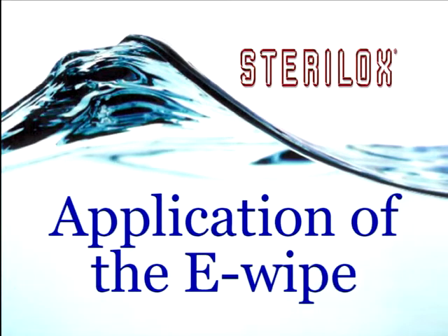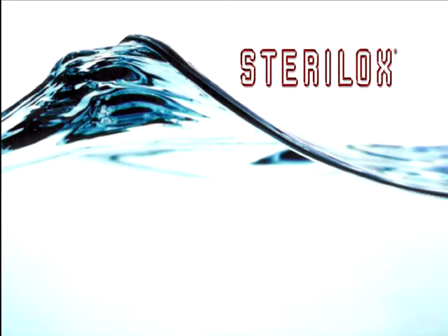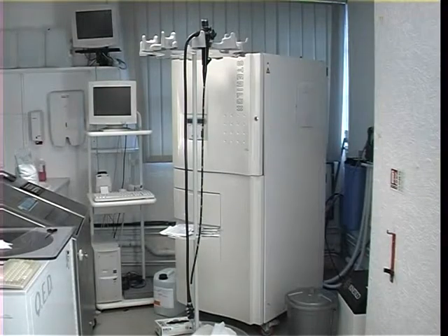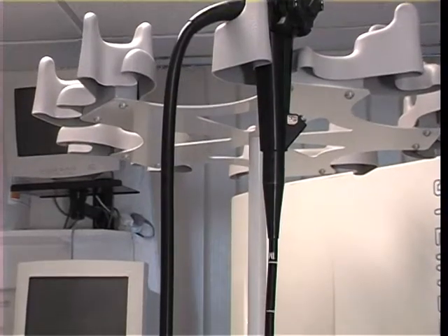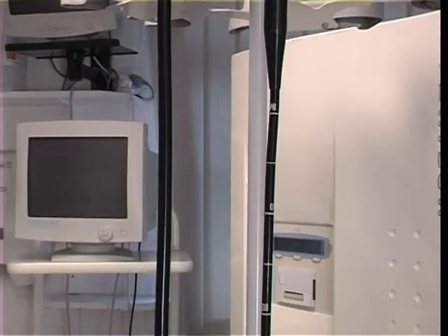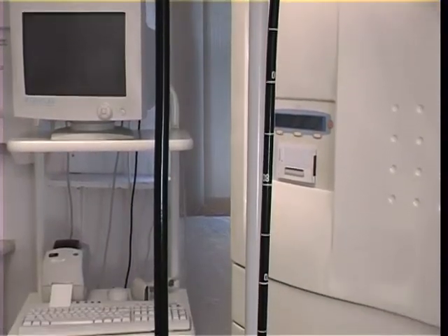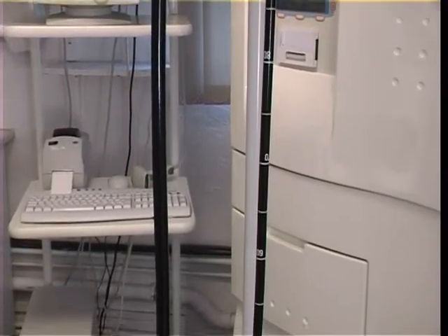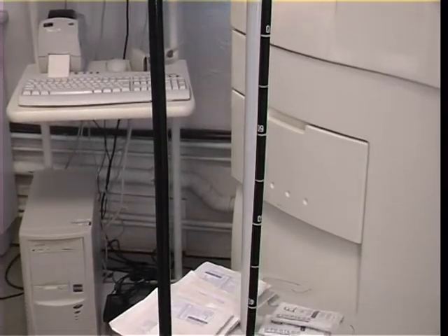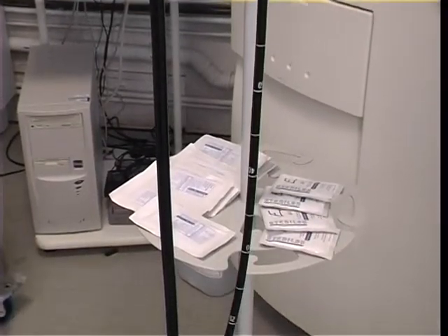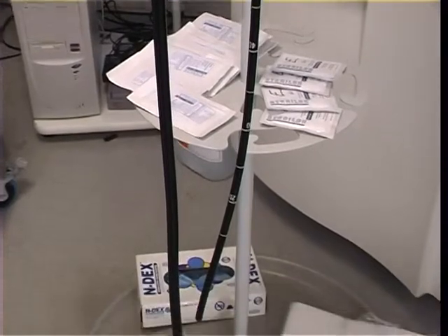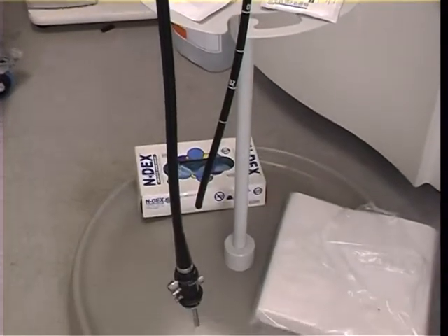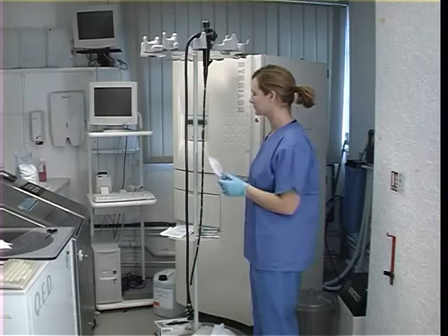Application of the e-wipe. You should firstly visually inspect your endoscope to ensure that the surface is in good condition and undamaged. If any damage is seen, the endoscope should not be wiped and you should phone either the endoscope technician or your area clinical advisor for advice. If you are happy that the endoscope is undamaged, then you can commence wiping.